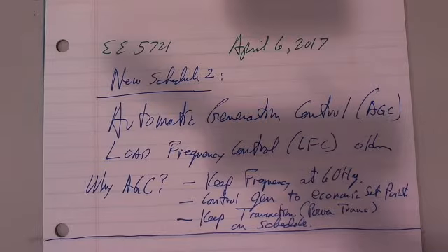That's very important. If you're buying 100 megawatts and your neighbor's supposed to be selling you 100, you don't want faulty equipment to have it turn out that you're only getting 98. And you're going to buy this for many hours. So, that's 2 megawatt error, let's say for 10 hours. That's 20 megawatt hours. That gets to be a little bit of money. And you want that contract to be met very closely. And AGC, that's another job that AGC fulfills. Okay.